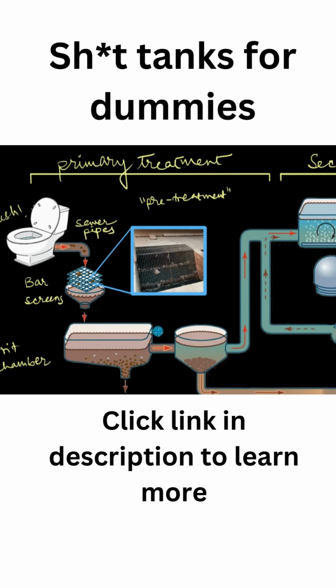And this is important because if you don't remove these things, they might go ahead and clog or destroy the pumps which are involved in this machinery. All the rocks and pebbles which are separated out in the grit chamber, that is the grit, it gets removed through this outlet right over here. So this is where the grit is removed from. This is the grit. The wastewater is then sent off to something called a clarifier, aka a settling tank. Now, since this clarifier is involved in primary treatment, we also call this the primary clarifier.